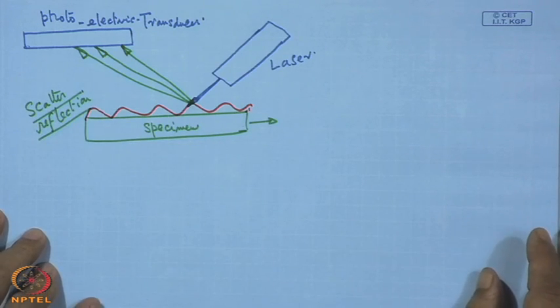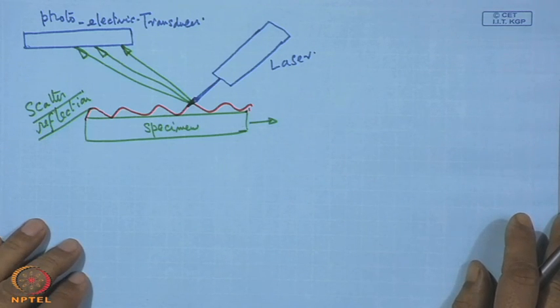So, this is another way, it is non-contact type. However, each system has its own merits and demerits. In this case, non-contact means that the radius of the stylus tip should not be a limitation, and this is rather high speed operation, the process is faster. Large area can be assessed rather quickly, such as parts coated in a steel mill or steel plant, galvanized parts, where it is of immediate interest to assess surface roughness. This laser beam reflection method is going to be one of the best candidates where we cannot use a contact type detector for assessment of surface roughness.